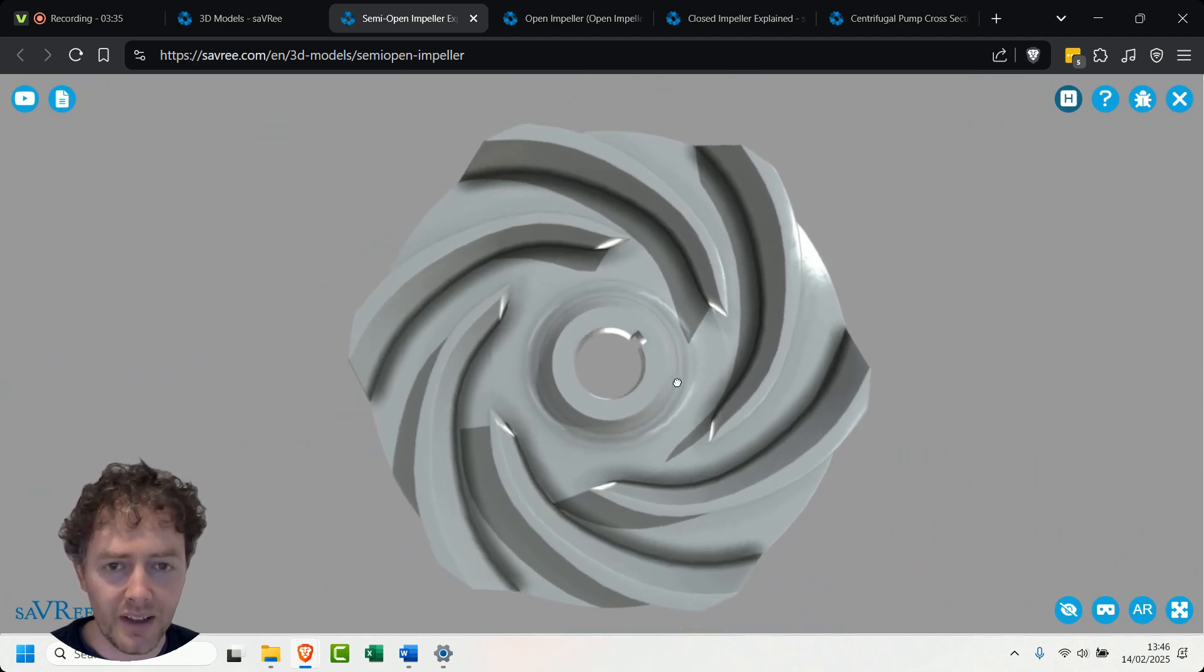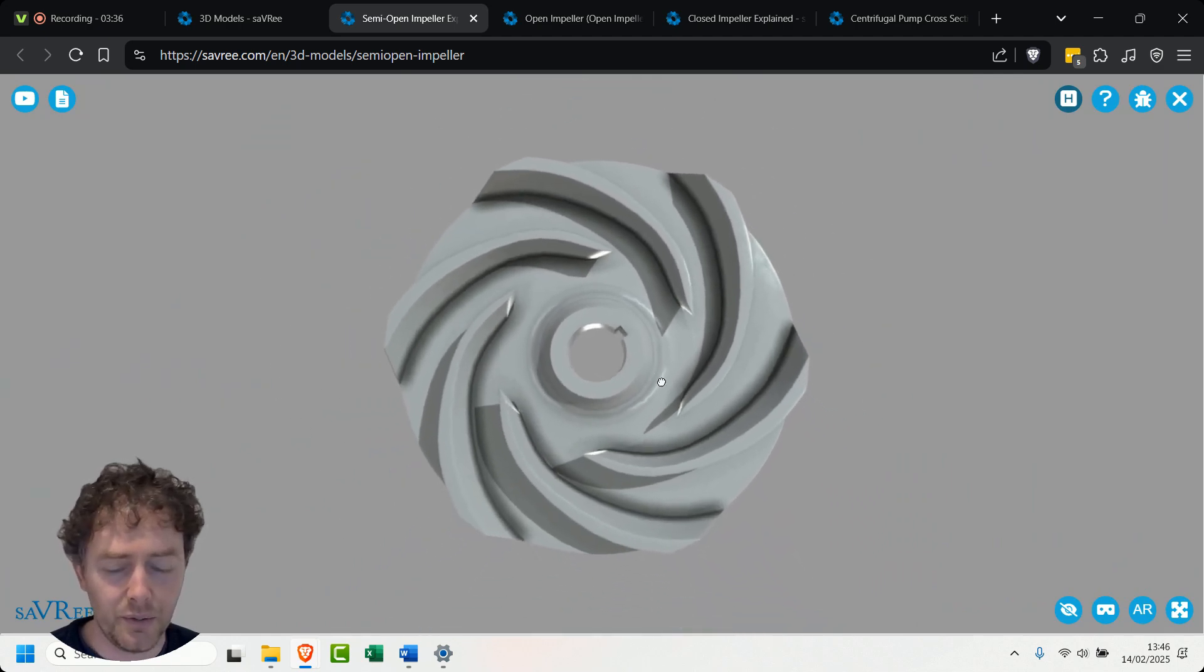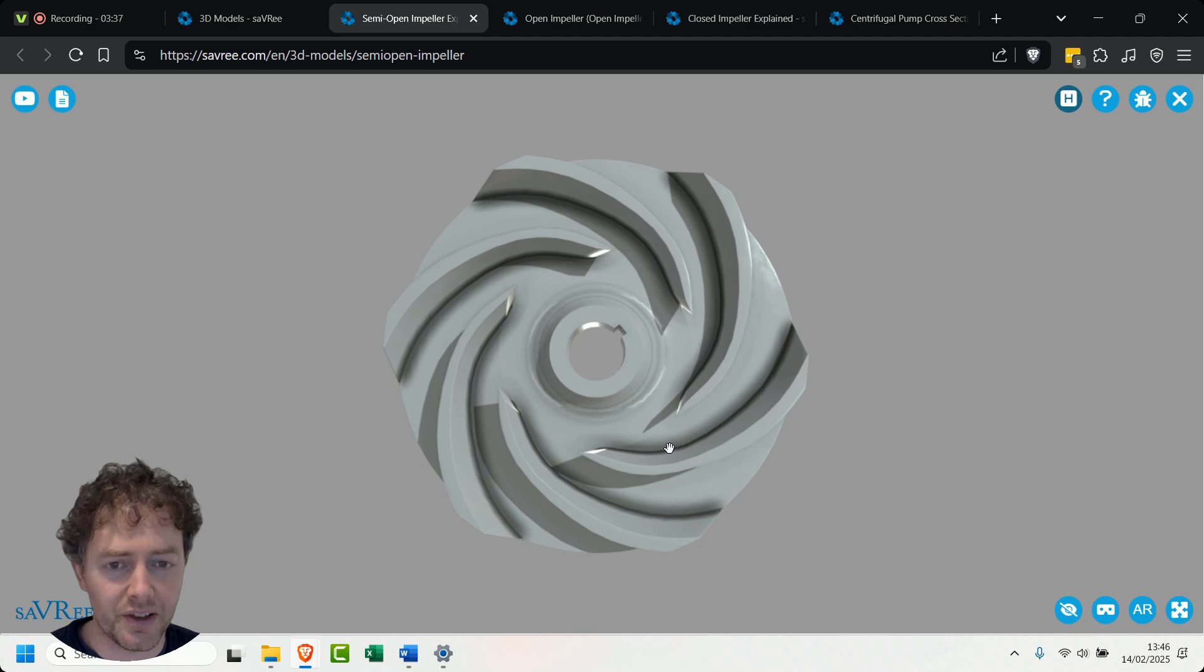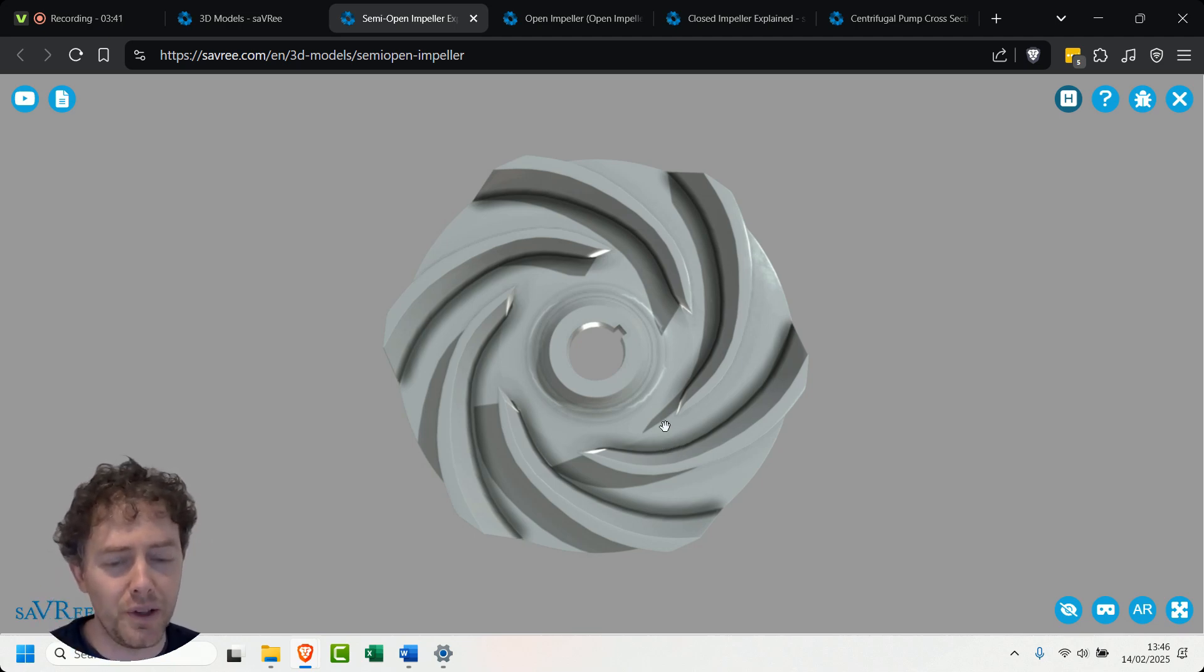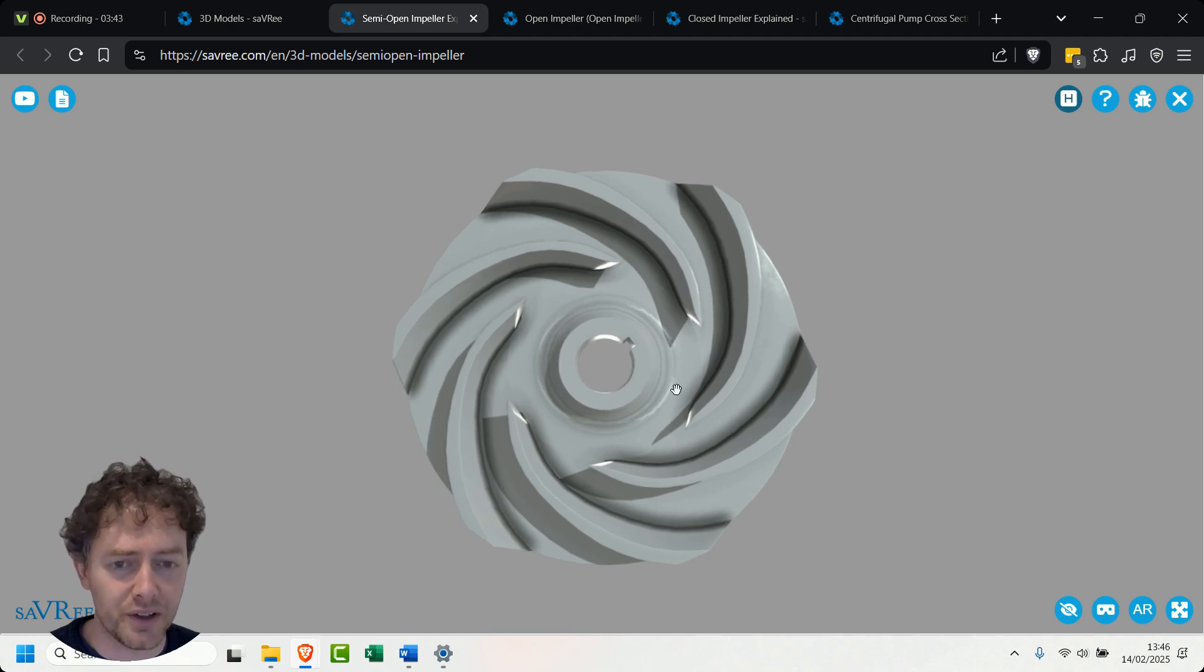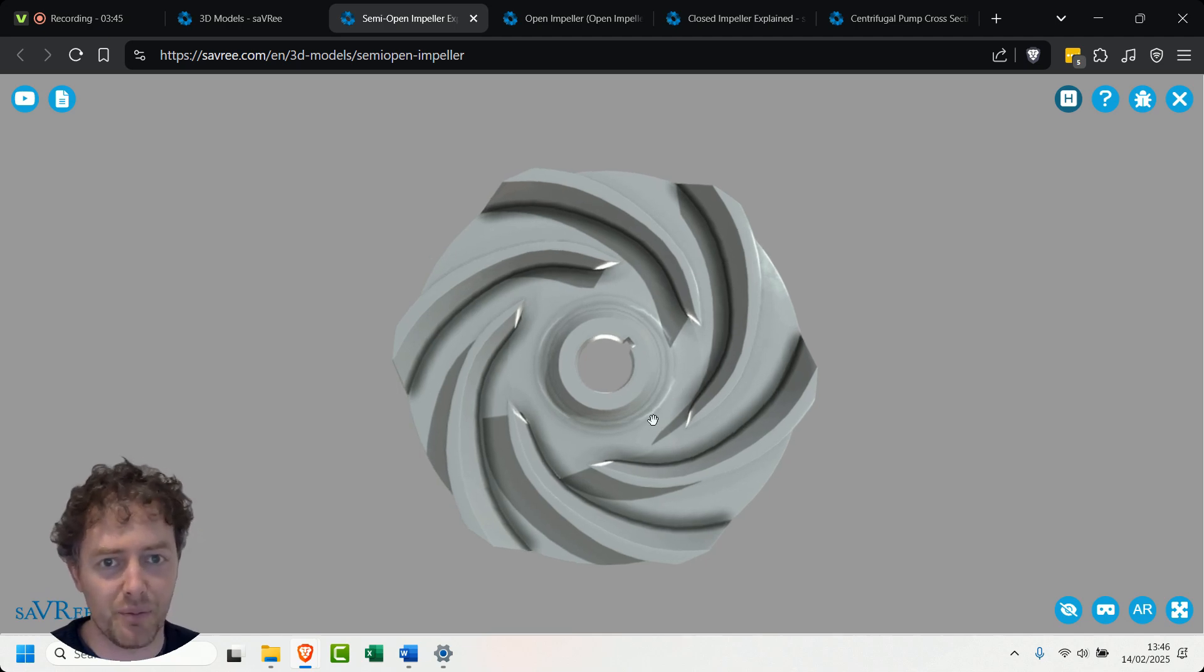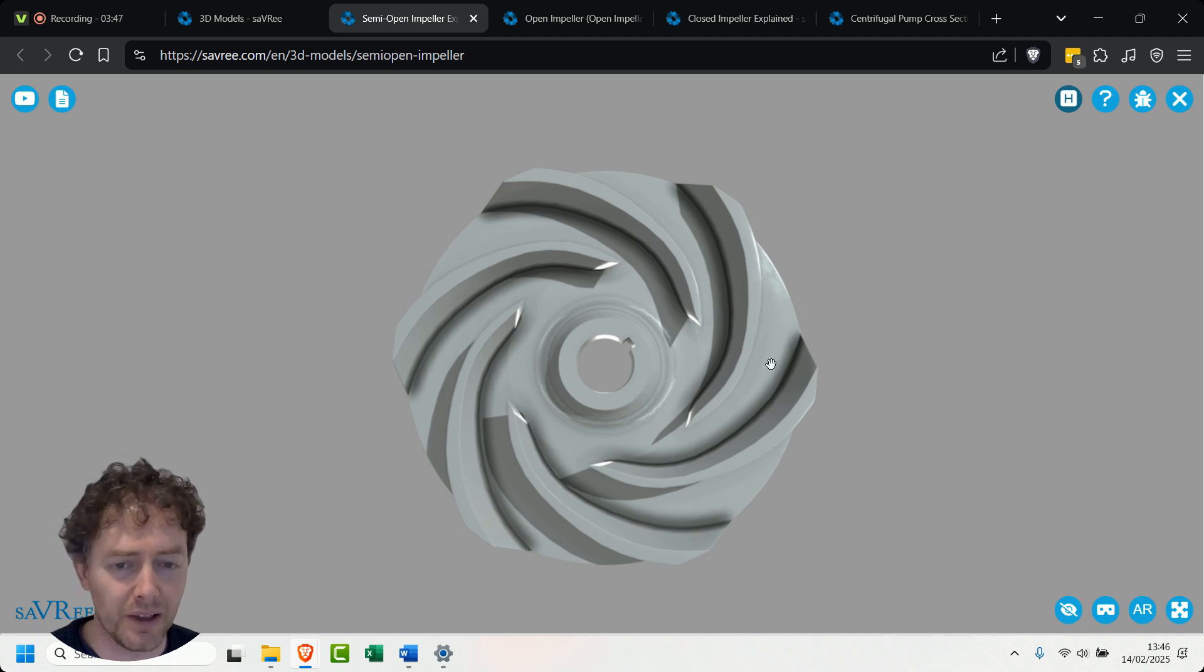Now when we've got this kind of shape like this one here we're going to use it for fluids that are maybe slightly more viscous although generally they're going to be pretty much the same as what we saw with the closed impeller. So we want a low viscosity fluid but this time around we can take a fluid that has more contaminants, more suspended bodies.